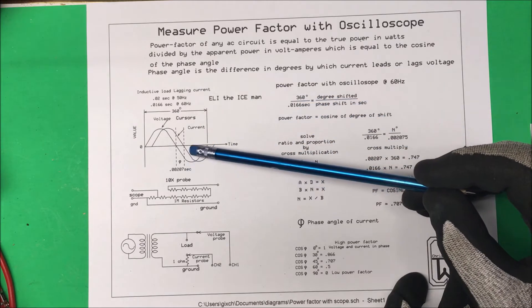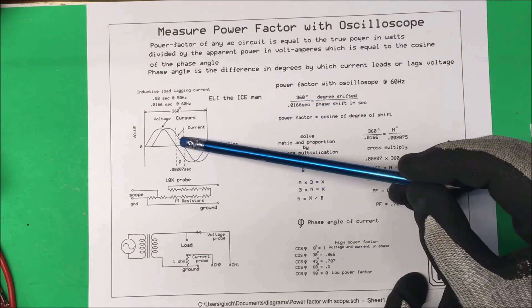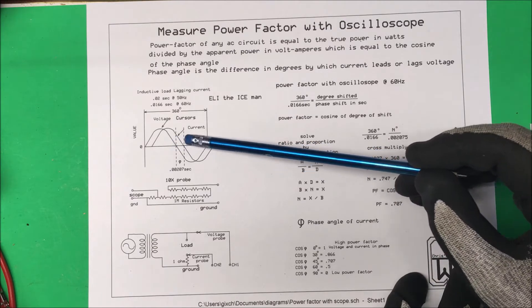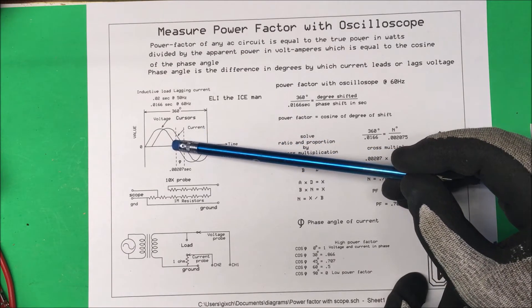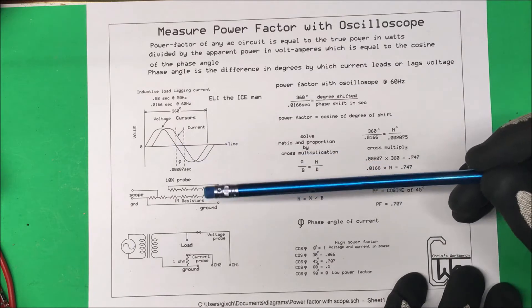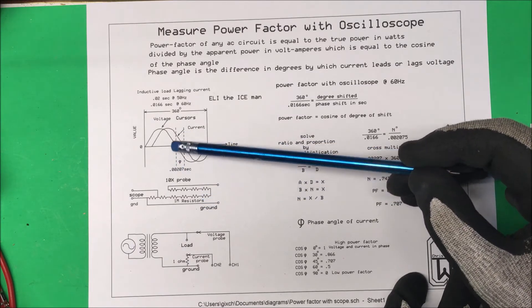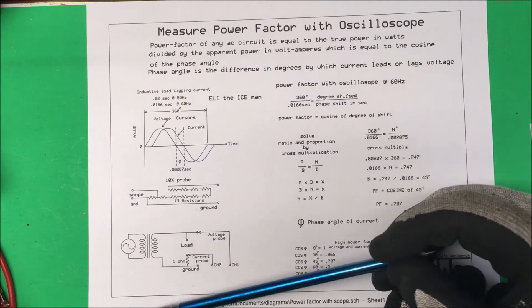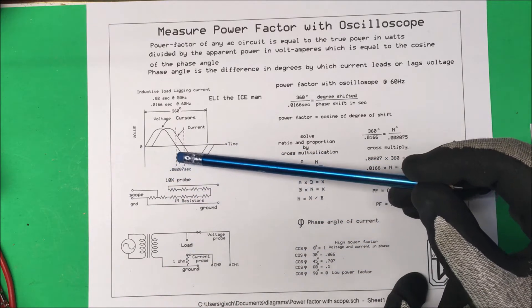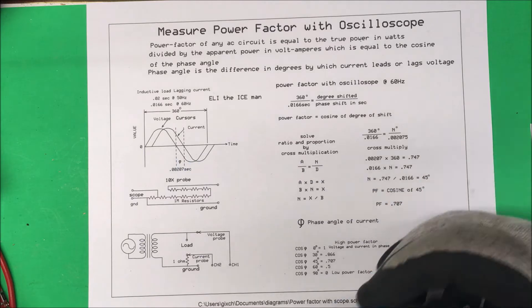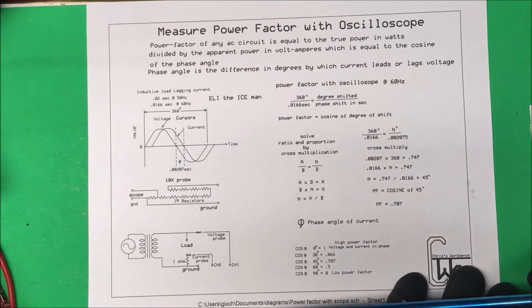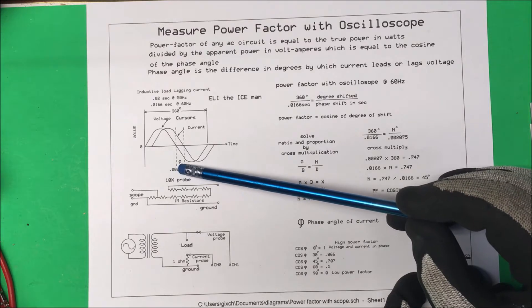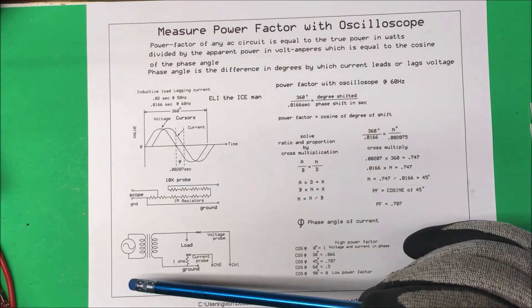We want to find the difference in time between these two sine waves, so we look at the zero crossing point and place a couple of cursors there. The scope shows 0.00207 seconds between the two crossings. We want to convert this to degrees and then take the cosine of that to find our power factor.